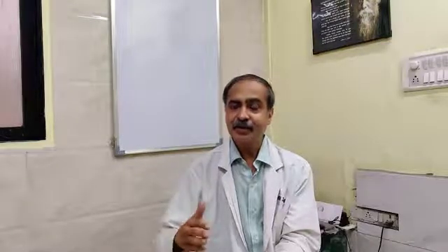Since the body of the patient forms part of a closed circuit, this closed circuit part should be kept as short as possible. So the passive electrode which is attached to the patient should be rostral to the operating side and closer to the operative side, so that the pathway within the body of the patient is short. It should never be close to the heart; particular care is to be taken in the case of a pacemaker patient.